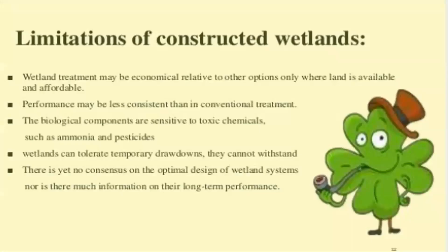Moving to the limitations of constructed wetland. Wetland treatment may be economical relative to other options only where land is available and affordable, which is most important because it requires a large amount of land. Performance may be less consistent than in conventional treatment, which involves a large process chain. The biological components are sensitive to toxic chemicals such as ammonia and pesticides, and there is no consensus on the optimal design of wetland systems, nor is there much information on their long-term performance.